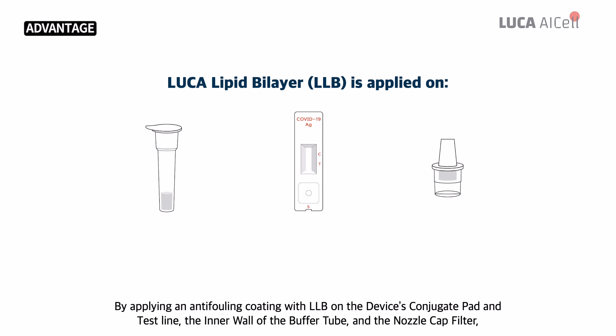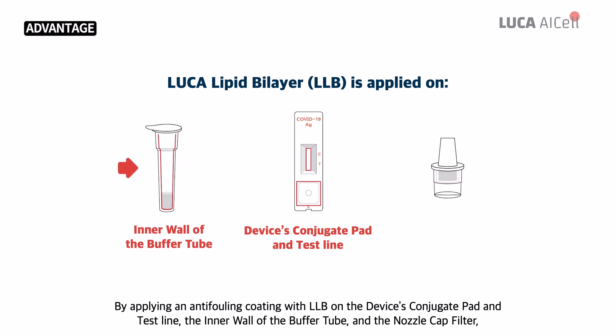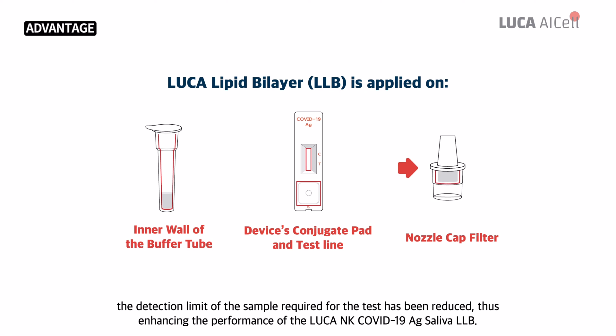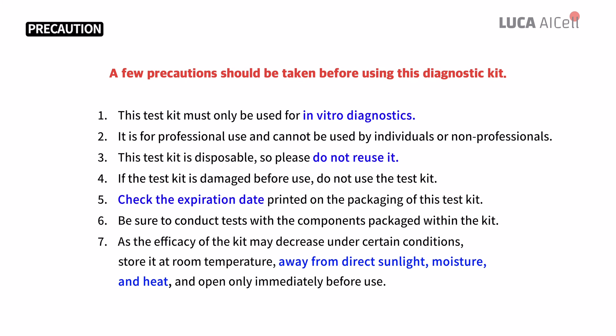By applying an anti-fouling coating with LLB on the device's conjugate pad and test line, the inner wall of the buffer tube, and the nozzle cap filter, the detection limit of the sample required for the test has been reduced, thus enhancing the performance of the Luca NK COVID-19 AG Saliva LLB. A few precautions should be taken before using this diagnostic kit.